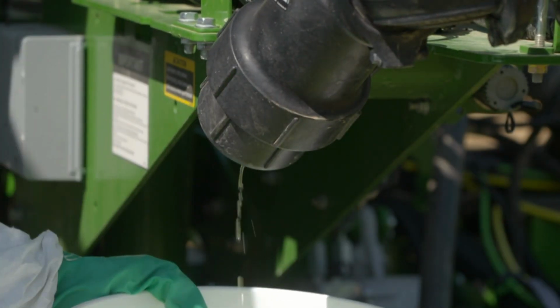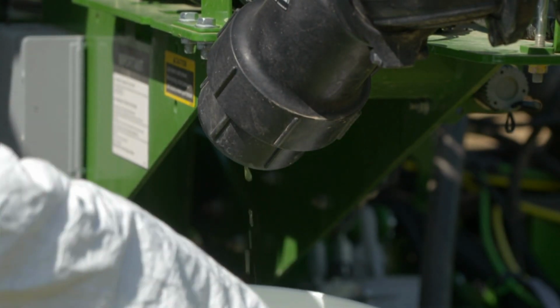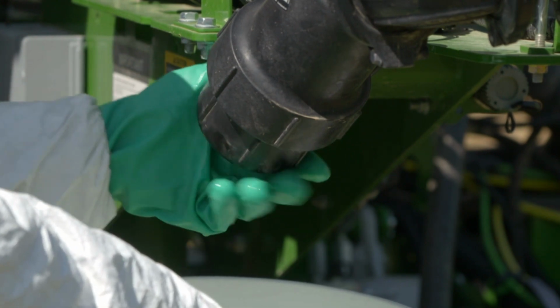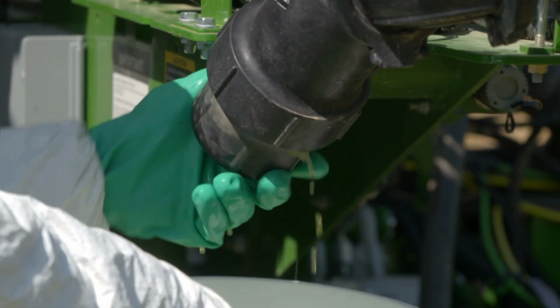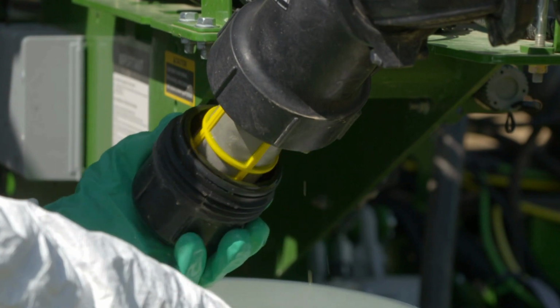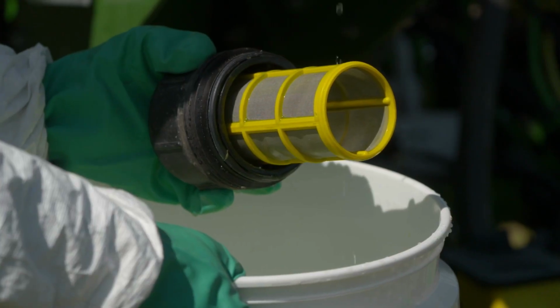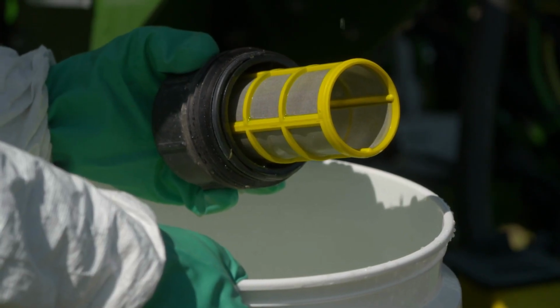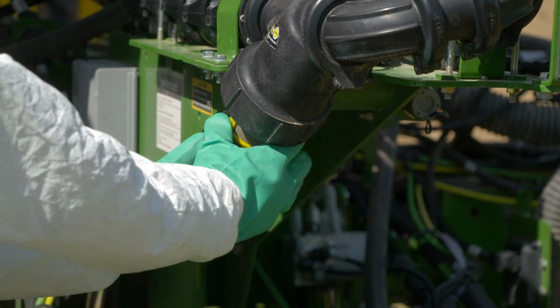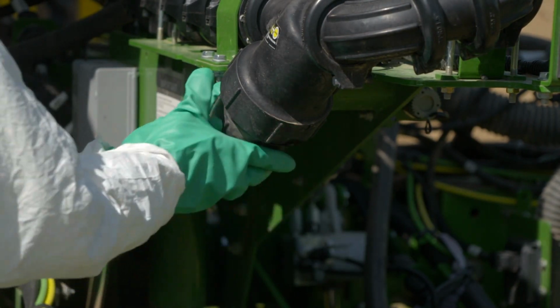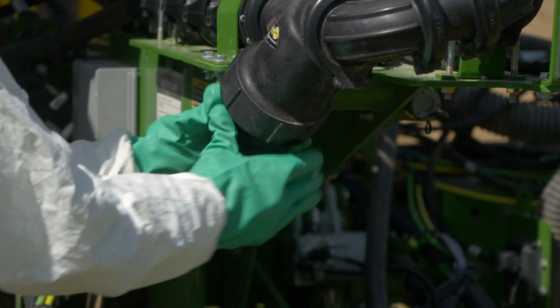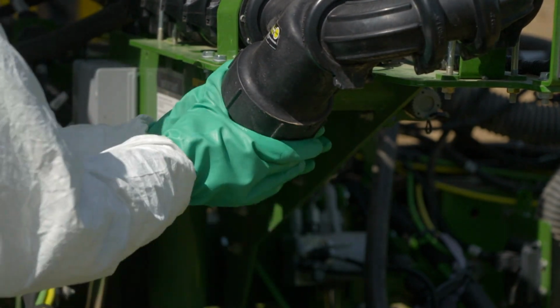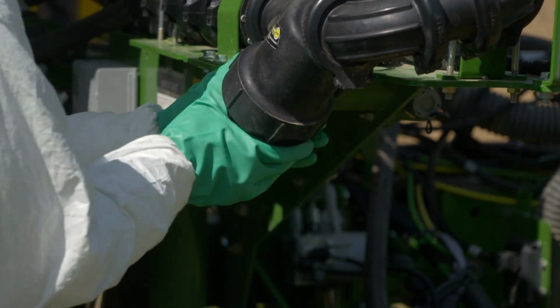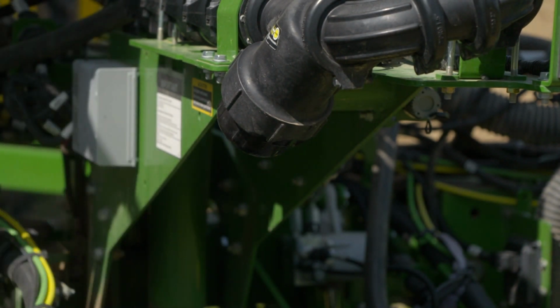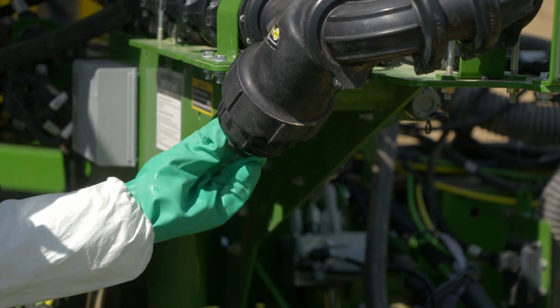Other causes of flow warnings include a plugged strainer. To remove the strainer, loosen the drain plug to allow the strainer to drain. Then remove the strainer cap and strainer. Clean the strainer with soapy water or replace as necessary. Install the strainer and tighten the cap. Then install the drain plug.